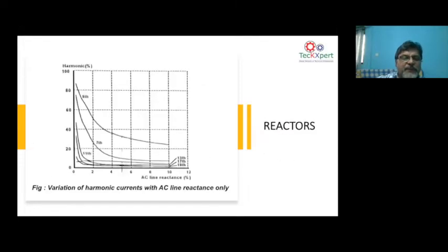Go to the next. As you can see in this, as you install different types of line reactors, you can see how the harmonics come down. For example, if you put a 2% line reactor, you can see the fifth harmonic is around 50%, and your seventh harmonic is somewhere around 30%. Now, let us say you put a 3% reactor, you can bring down your fifth harmonic. If you look at your fifth harmonic graph, with a 3% reactor in the middle, between 2 and 4, you can see your fifth harmonic can come down to about 40%.